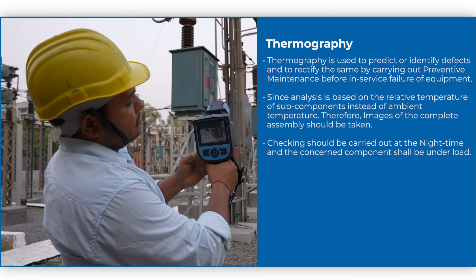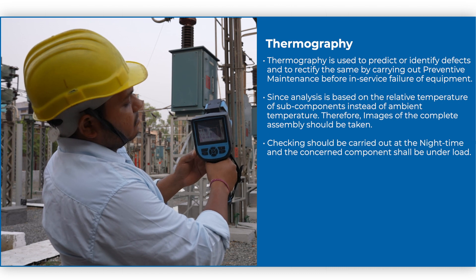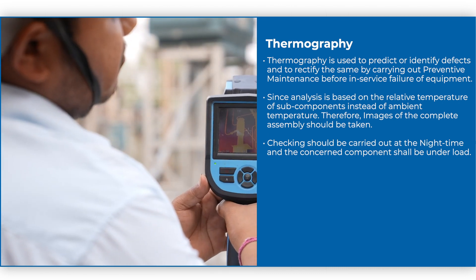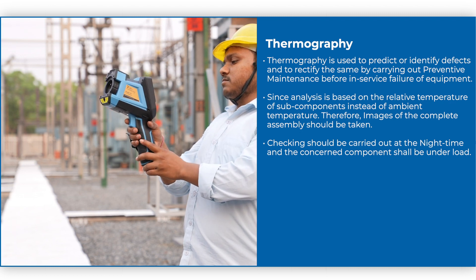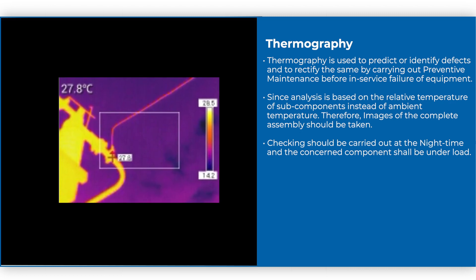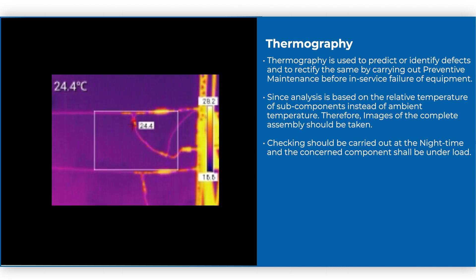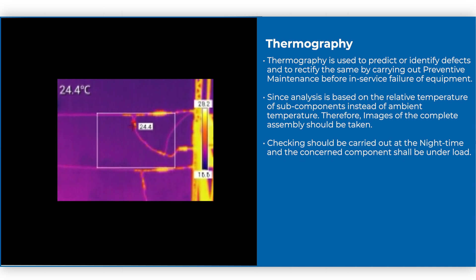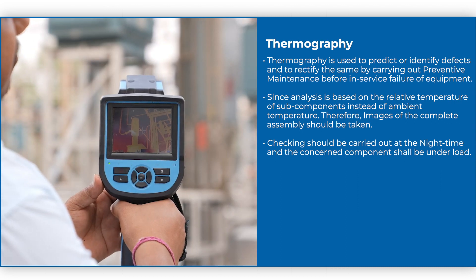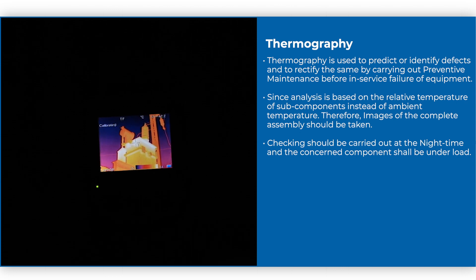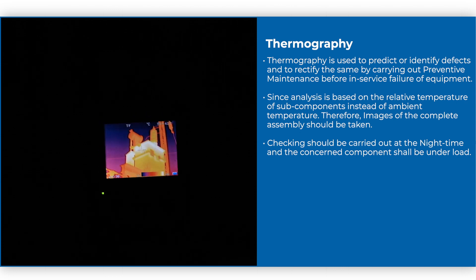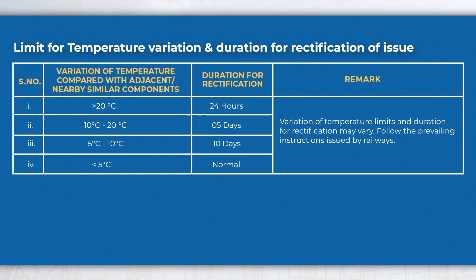Thermography: Thermography is used to predict or identify defects and to rectify them by carrying out preventive maintenance before in-service failure of equipment. Since analysis is based on the relative temperature of subcomponents instead of ambient temperature, images of the complete assembly should be taken. Checking should be carried out at night time and the concerned component shall be under load. The limit for temperature variation and duration for rectification of issue is given in the table.